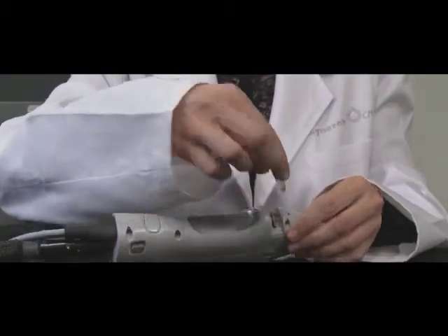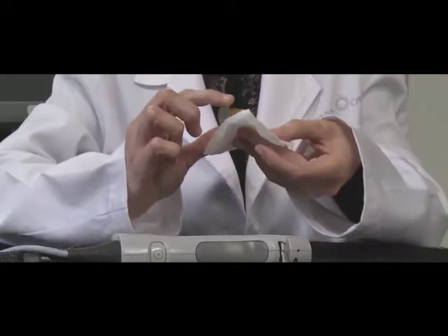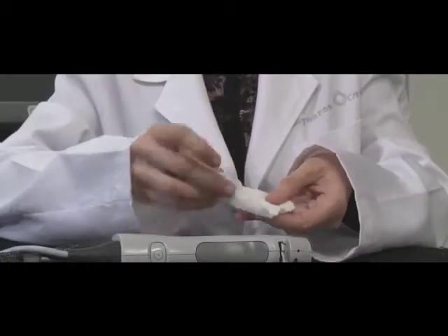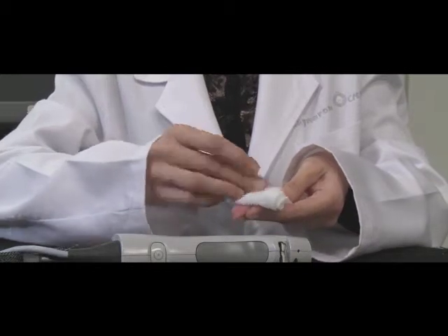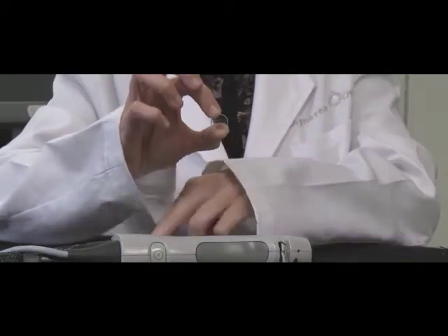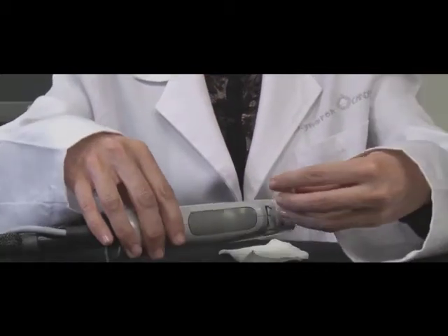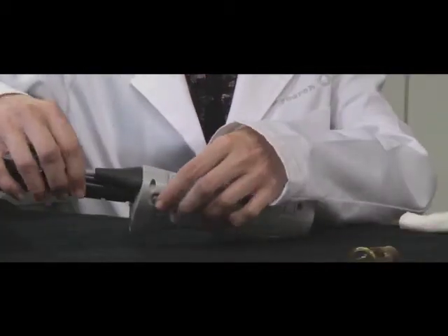The window should be changed approximately every 200 to 300 pulses, at the same time as you switch out the distance gauge. In order to change the window, simply slide out the window holder and replace the window. All windows and distance gauges can then be cleaned at the same time at the end of the treatment session.